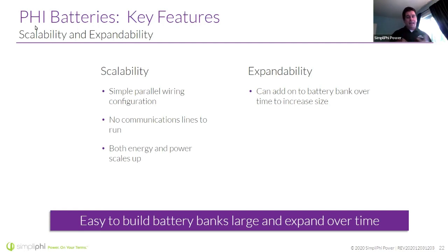Another aspect is expandability. With certain battery chemistries, it's not recommended to expand a bank after it's commissioned, because doing so limits anything you add to the bank's ability to the lowest common denominator, the oldest battery in the bank. To a certain extent that's true for ours as well, but you can expand, we'd say, up to about the 2 year mark or so, depending on usage.